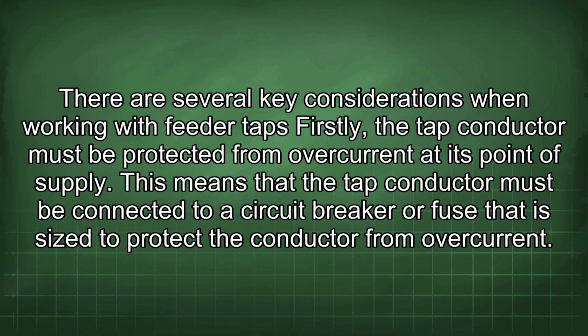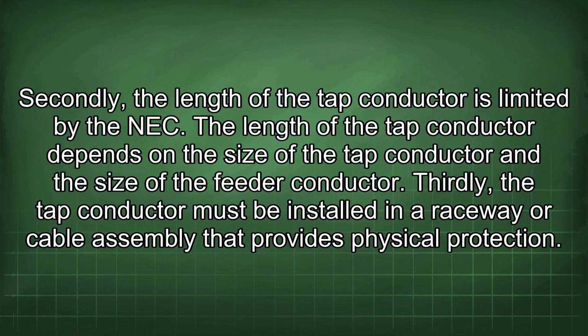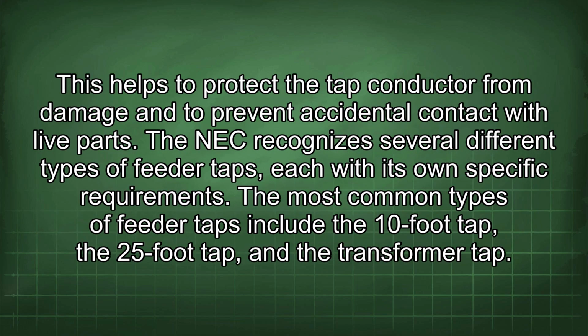There are several key considerations when working with feeder taps. Firstly, the tap conductor must be protected from overcurrent at its point of supply. This means that the tap conductor must be connected to a circuit breaker or fuse that is sized to protect the conductor from overcurrent. Secondly, the length of the tap conductor is limited by the NEC. The length of the tap conductor depends on the size of the tap conductor and the size of the feeder conductor. Thirdly, the tap conductor must be installed in a raceway or cable assembly that provides physical protection. This helps to protect the tap conductor from damage and to prevent accidental contact with live parts.